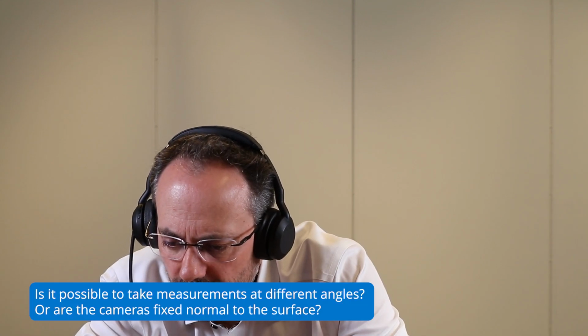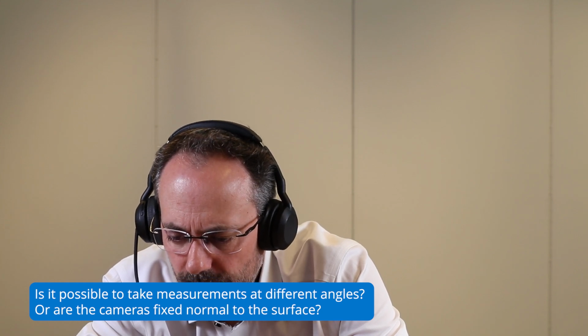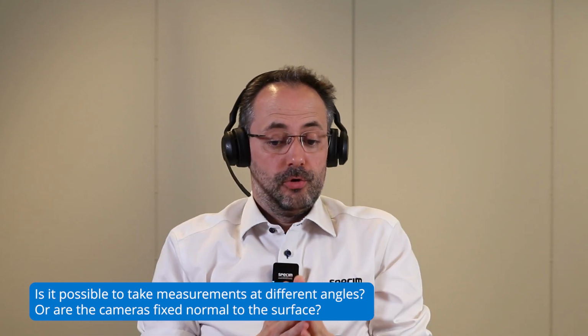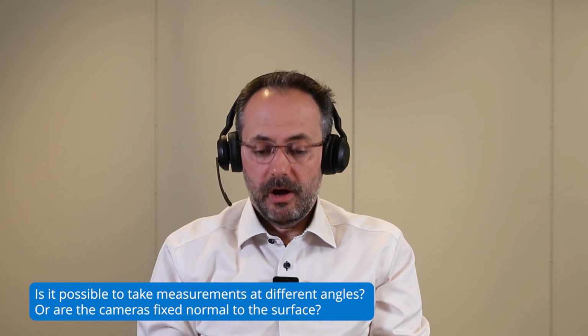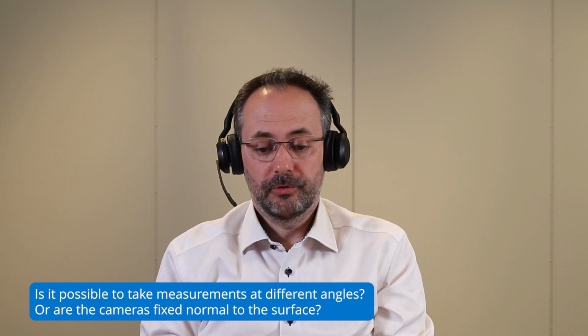Is it possible to take measurements at different angles, or is the camera fixed normal to the surface? No, you can put the camera as you want, and there are actually applications which benefit from what we call specular geometry. So you can have the illumination going to the sample, and then have the camera looking directly like this, as if it were in a mirror. This is, for example, the typical way when you are dealing with shiny black plastic. It is a typical way to deal with samples in general which are not diffuse, so that means that they don't reflect in every direction, but are really directional like this.